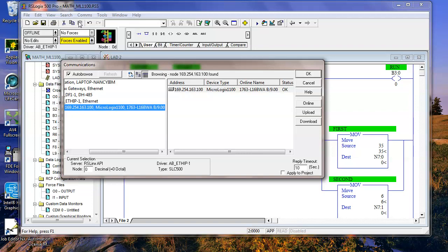By the way, and we had this happen a couple of times already, you cannot duplicate, normally, you cannot duplicate output addresses, right? You understand that? So this has happened a couple of times where I got called back there and they say, well, the rung's true, but the output don't go true. And what's been wrong both times? They had that same output down here. So this rung up here was false. This rung down here was what? I mean, true. So your computer don't know what to do with it. So be careful on that.